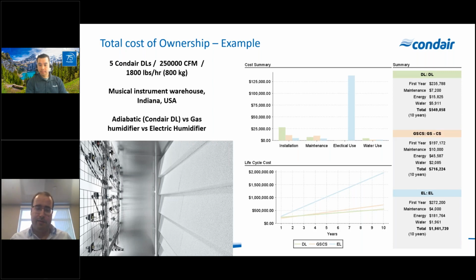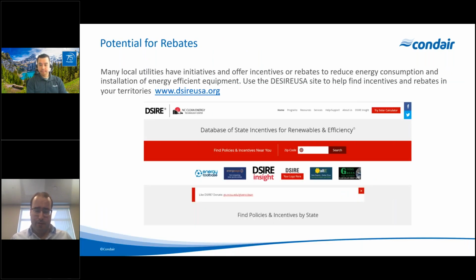That's one of the things - even if people have old steam, they can retrofit with some of the adiabatic technologies, and typically the payback is actually very low, especially if it's a cold climate where they run the humidification for 3,000 hours a year, let's say. They have a big season. It's very, very low. And especially if you already have treated water on site, being RO or DI or ultra pure water, then your payback is even lower because you don't have to invest in that part of the equipment.